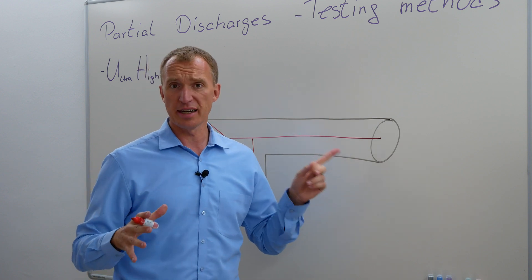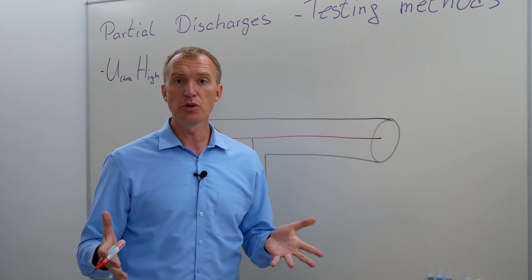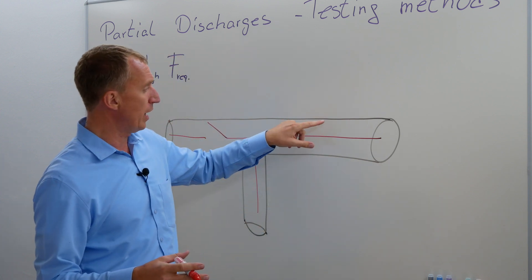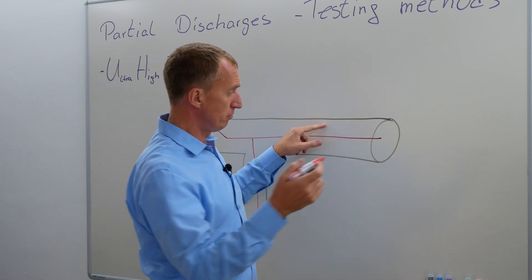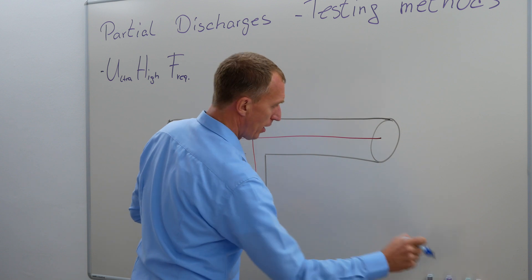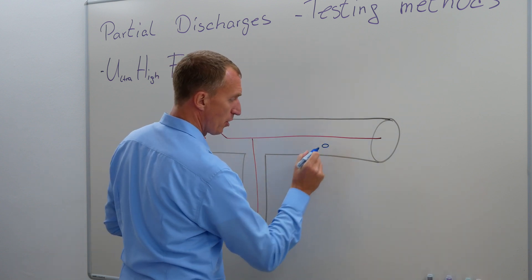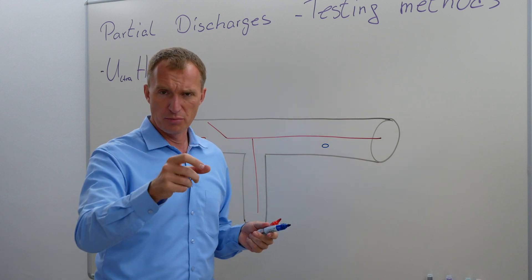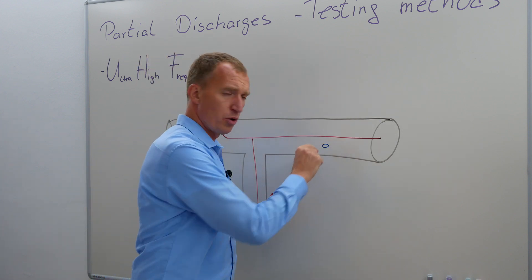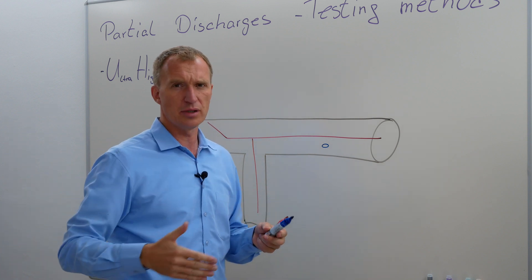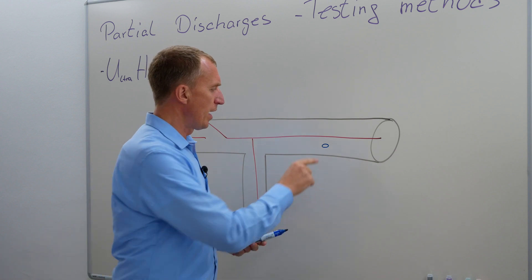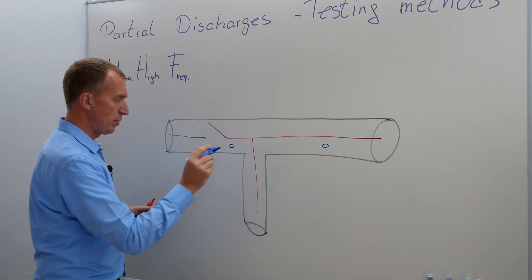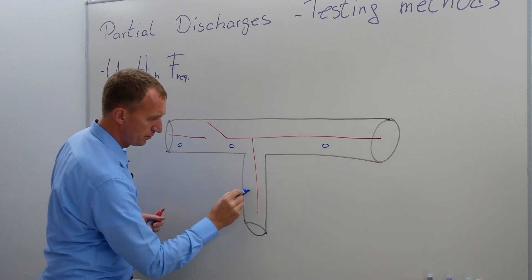If you want to measure inside the GIS, you have the possibility to use UHF sensing as well, so ultra-high frequency testing. What you can do is, you have two approaches if you want to use UHF. Either there are these small windows over here that allow you to look inside, but the most important thing is, they have a small hole in the metal encasement, and they have some kind of insulation material, something like acrylic glass. You can place a sensor here, and maybe you have another one here, or maybe here.